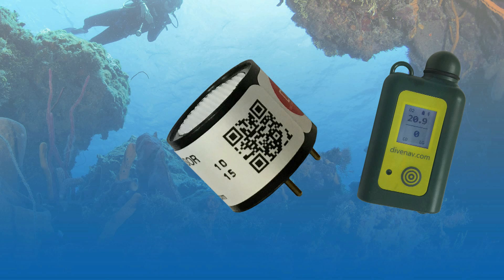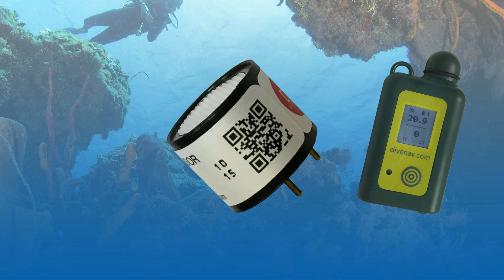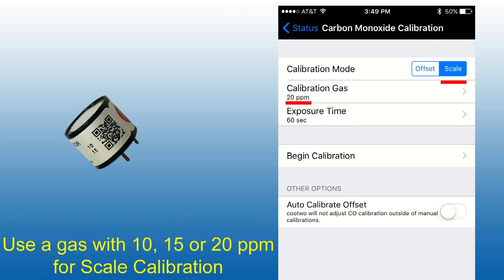The calibration of the carbon monoxide sensor requires the use of two different reference gases. A reference gas containing zero ppm is required to set the offset value, and a reference gas with either 10, 15, or 20 ppm is required to set the scale value.